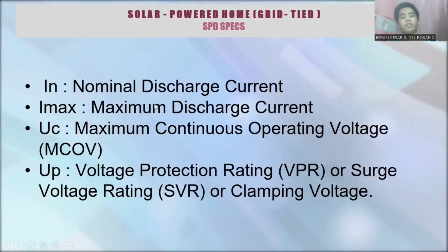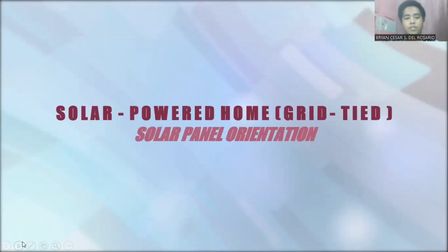So ano ba yung SPD specs? Ito yun. Yung In, meaning nominal discharge current. Yung Imax naman is maximum discharge current. Yung UC, ito yung kanina, maximum continuous operating voltage o yung MCOV. Next, yung Up, voltage protection rating VPR or surge protection rating SPR or clamping voltage.